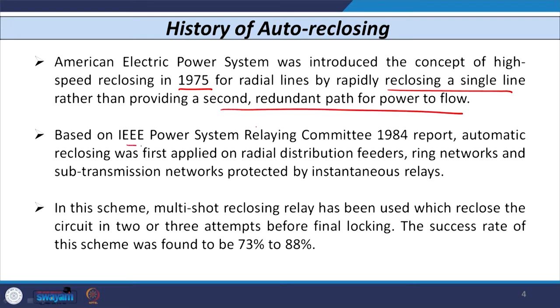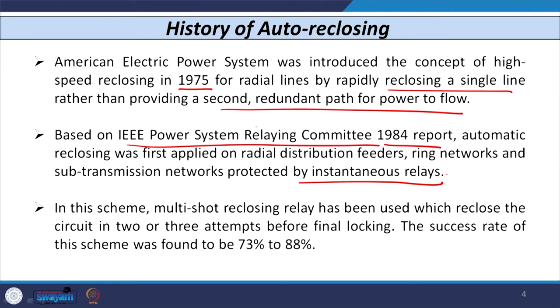The IEEE Power System Relaying Committee in a 1984 report mentioned that auto reclosing systems can be applied on radial systems, ring networks, and sub-transmission and transmission networks using instantaneous relays — whether instantaneous overcurrent relays, distance relays in the first zone, or pilot relays. In this scheme, a multi-shot reclosing relay is used, and the success rate was found to be around 73 to 88 percent, tremendously increasing service continuity and system stability.